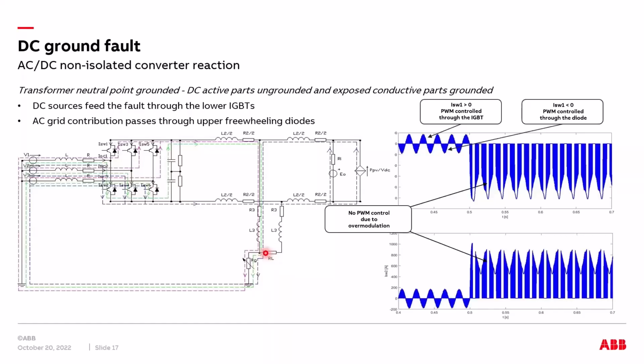Here we can have, if the vehicle is connected to the PE system, so it is not ungrounded, even if the battery installed on our vehicle is ungrounded in terms of active part, a reclosing path through the neutral point connection to the ground of our medium voltage/low voltage transformer, in particular of the low voltage windings, if they are connected to the ground. As you can see, also in this case, we can have a triple contribution.